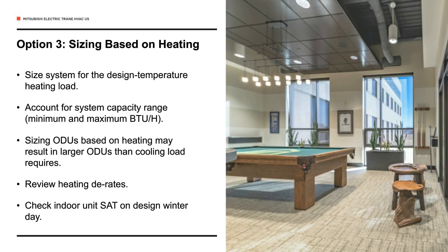Option 3 is similar to option 1, using the flash injection product, except we're just doing this with the standard product now and oversizing such that we have the required heating capacity that we need. And this is generally done in climates that get cold, but not as cold as places like, say, Chicago. So when we do this, we need to make sure that we look at the heating derates. You can either use the charts, which is getting rarer and rarer for people to use the engineering manuals and the derate charts, or what's most common now is people use the manufacturer's selection software to rate these. So you can build these units on an as-configured basis and look at actual heating derates and cooling derates based on your design temperatures for both winter and summer.